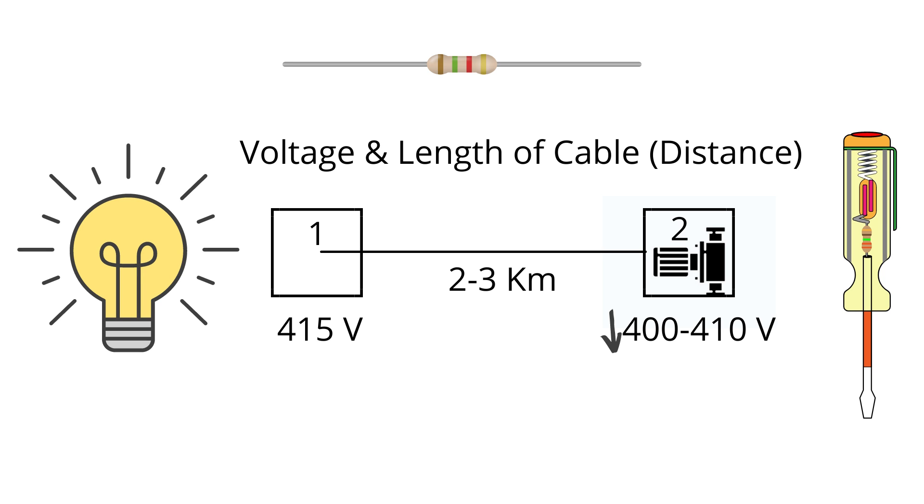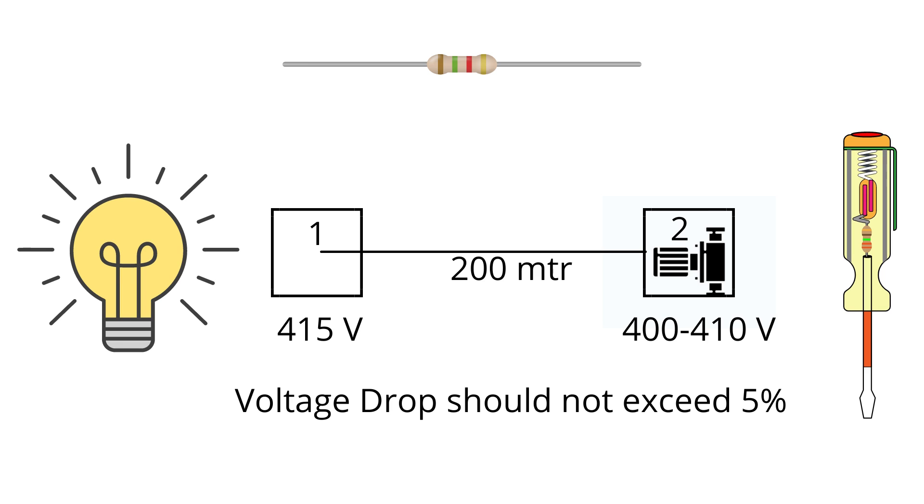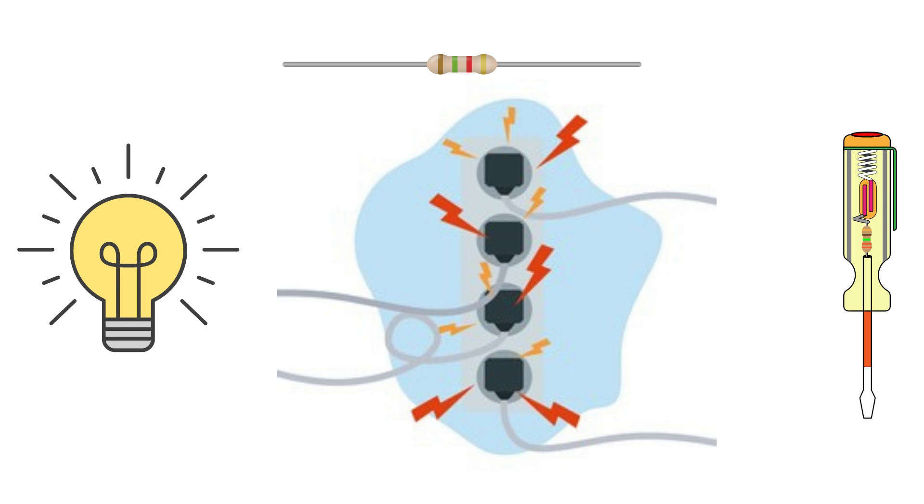To prevent this huge loss in voltage, we can increase the supply voltage from 415 volts to 11 kV. An important point to note here is that in any electrical system, drop in voltage cannot be greater than 5%, or else that system would be deemed inefficient.